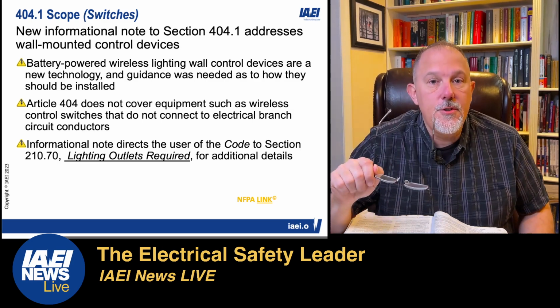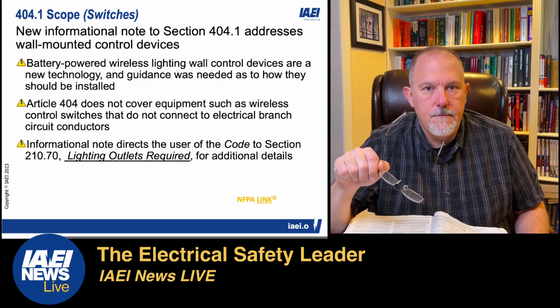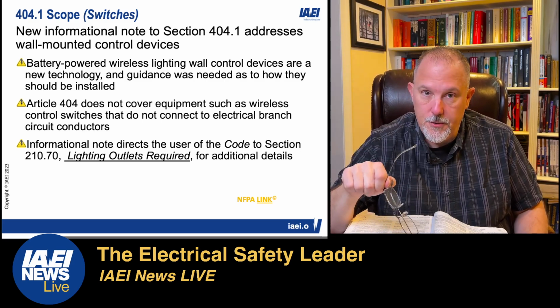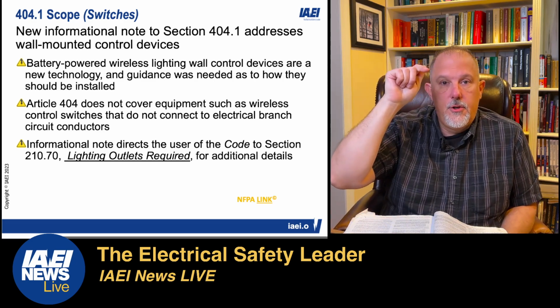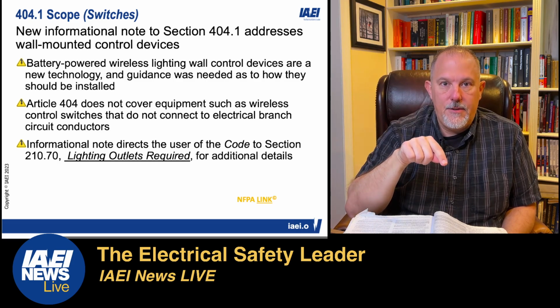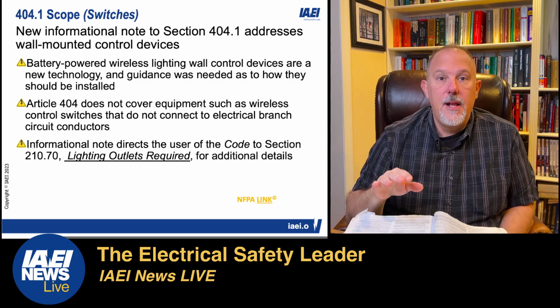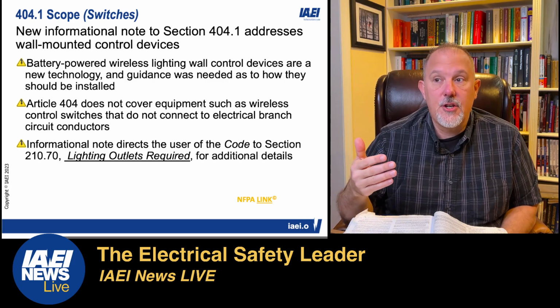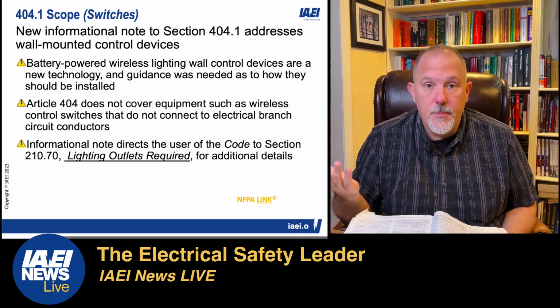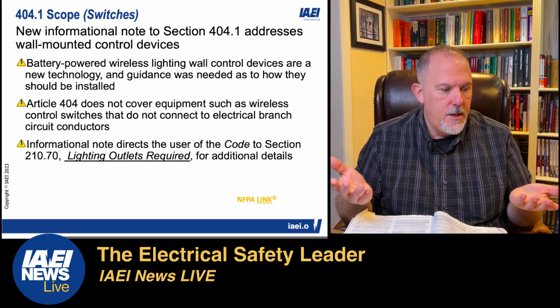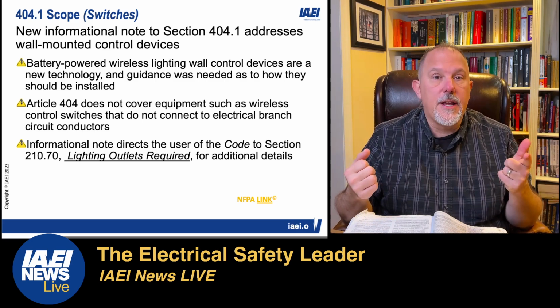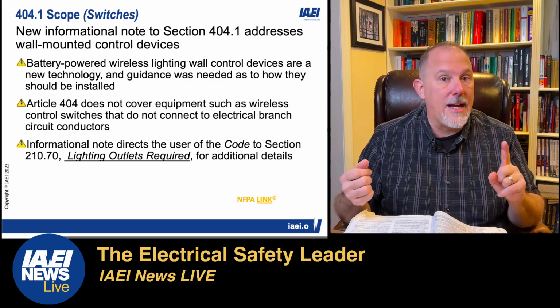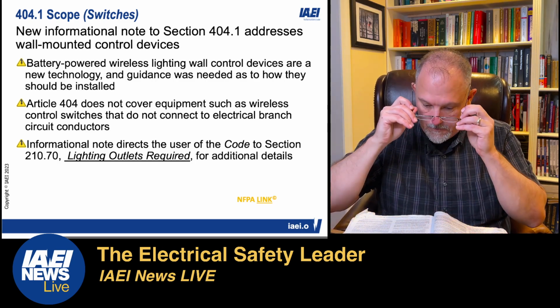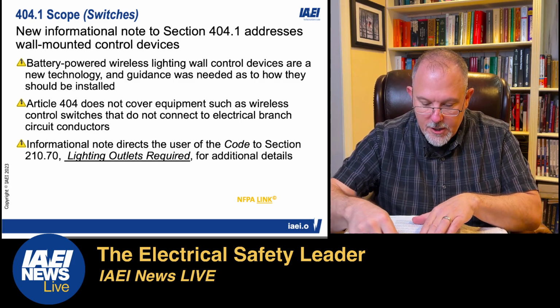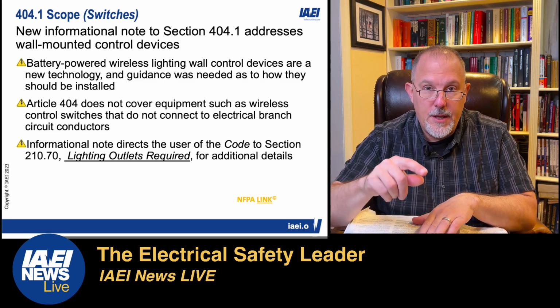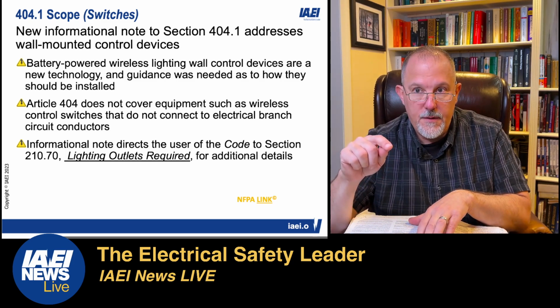So we introduced a new technology which would not require you to pull a conductor from the branch circuit to the lighting switch. You don't need to land a conductor on this because it's just a listed wall-mounted control device that could be wirelessly controlling the bulb or the fixture. I mean, there are these bulbs that are smart, but we'd have to look at whether or not that would be permitted, because I don't believe that would be the case, because it says at least one lighting outlet controlled. So you have to control the outlet. You can't just control the lamp, right?